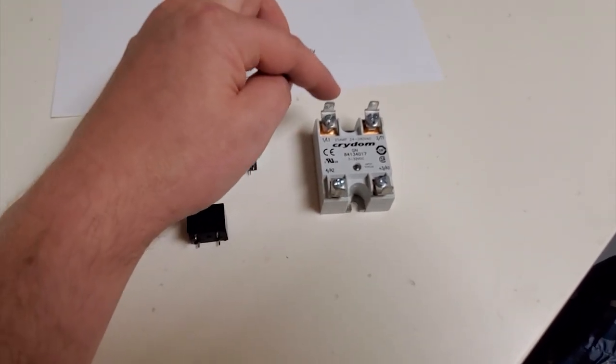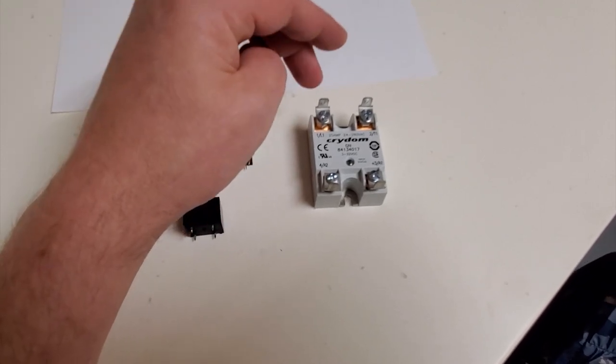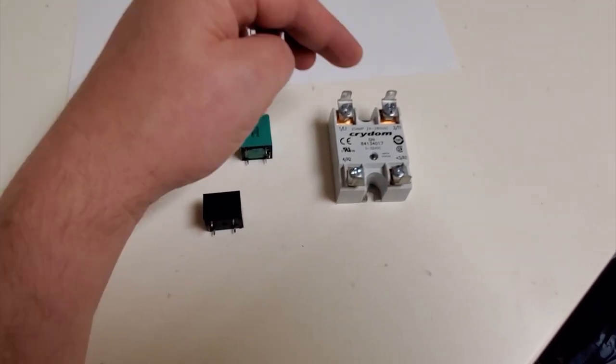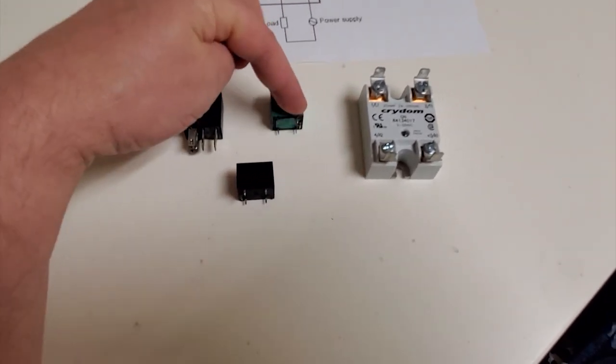And the way to troubleshoot the output side is you take a voltage measurement with your multimeter. Now, since this is a triac, there is going to be a voltage drop of a volt to two volts. Unlike a mechanical relay, where you're going to have zero volts potential difference between the output pins.